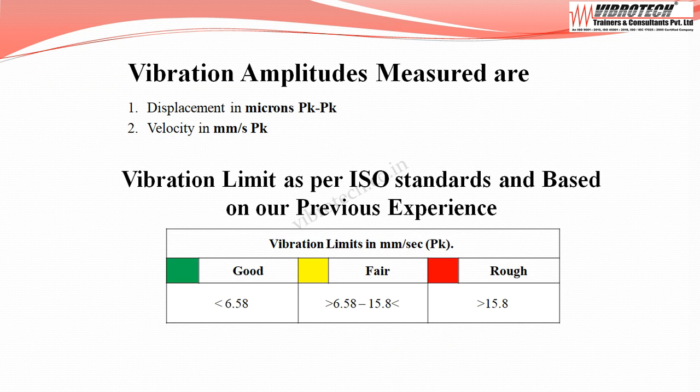Vibration data are collected in terms of displacement in microns peak-to-peak and velocity in millimeters per second peak. As per ISO standard and previous experience, when velocity falls below 6.58 mm/s peak it is considered good; between 6.58 and 15.8 mm/s peak it is considered fair; and above 15.8 mm/s peak it is considered rough.